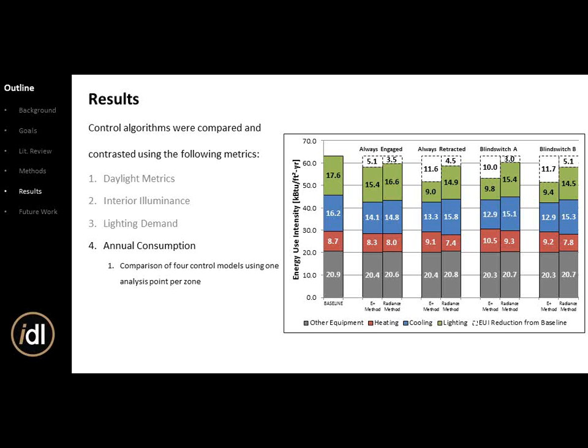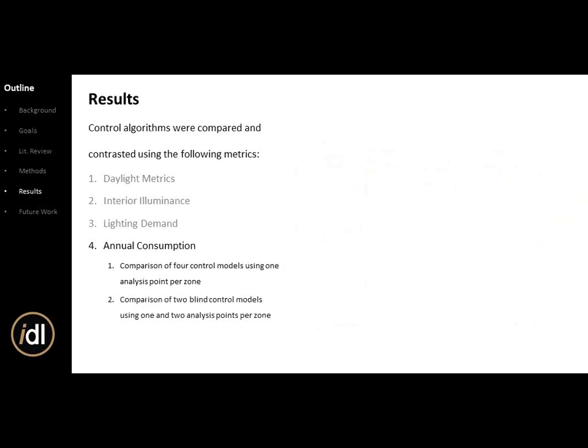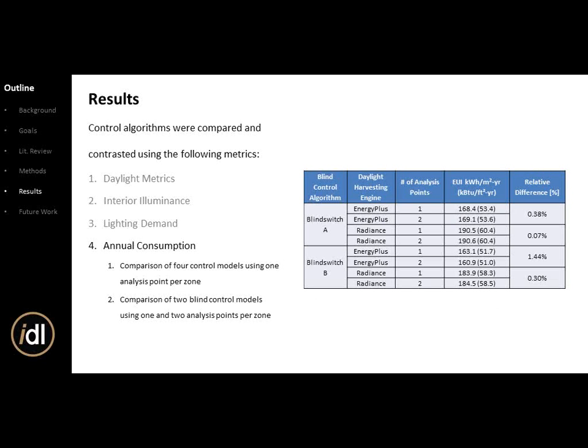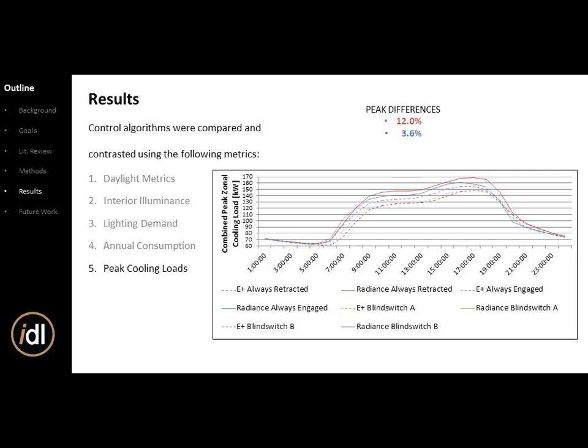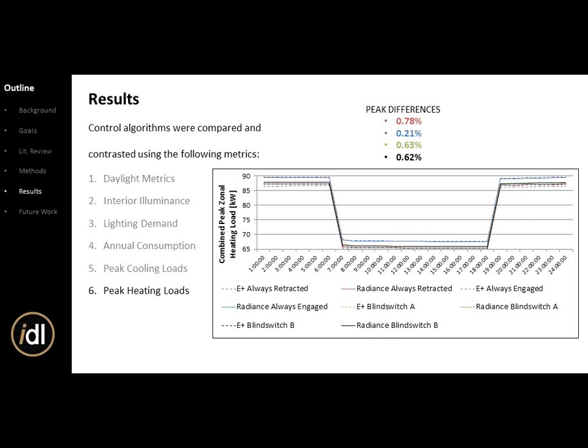Annual consumption comparison shows EnergyPlus on the left and Radiance on the right for each run. Overall, EnergyPlus over-predicts energy savings due to conservation measures, so it's important to note it's not perfect. We also compared one versus two sensors per zone — there's at most a 1.44% annual energy consumption difference, so you really don't need multiple sensors. Cooling loads are somewhat affected, and heating for always retracted versus the baseline is about 0.7%, so not a major factor.